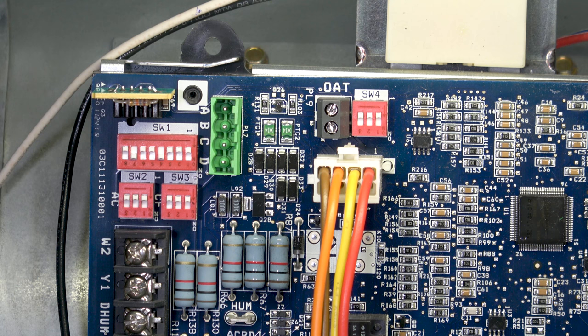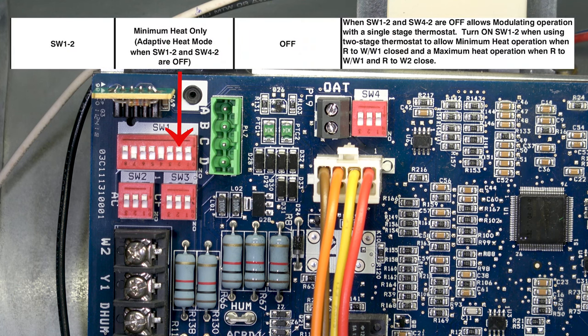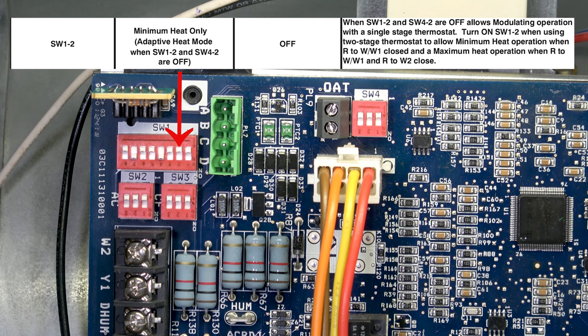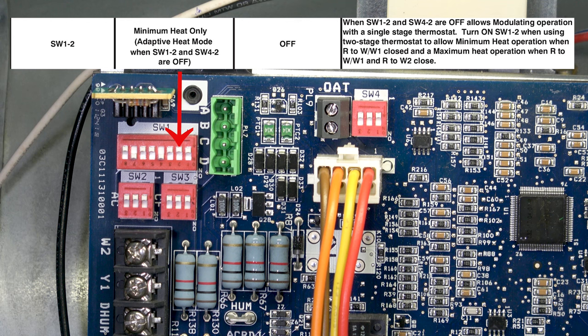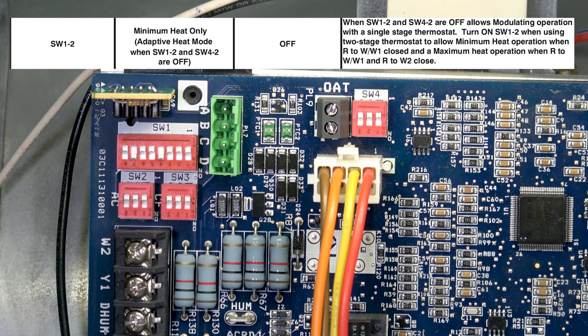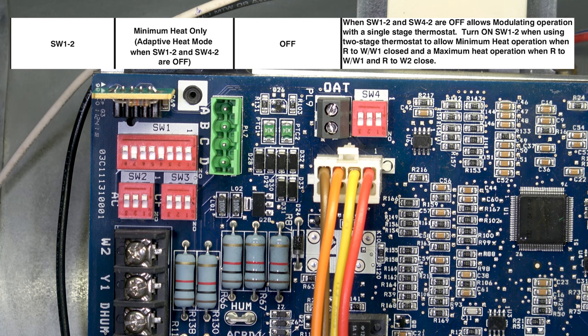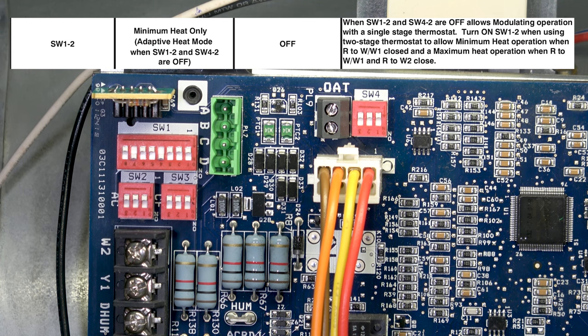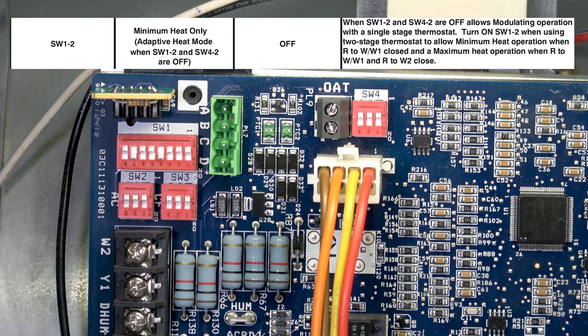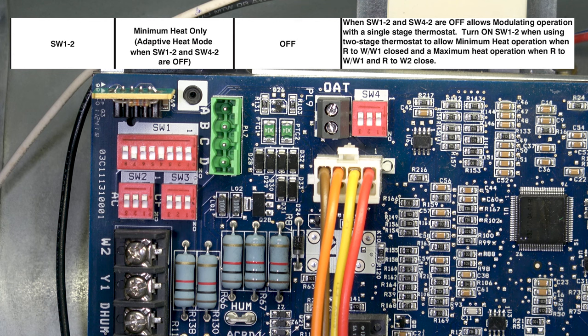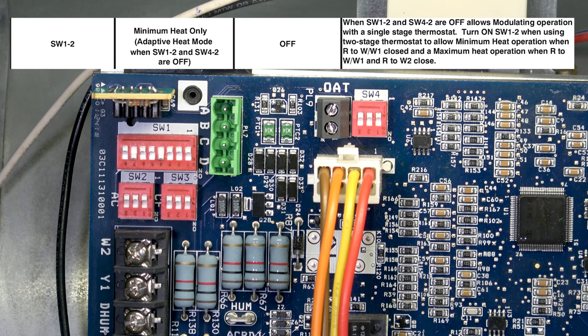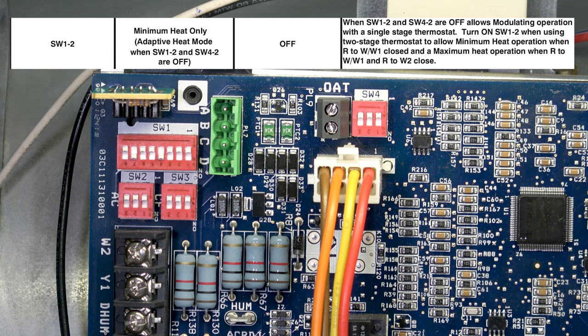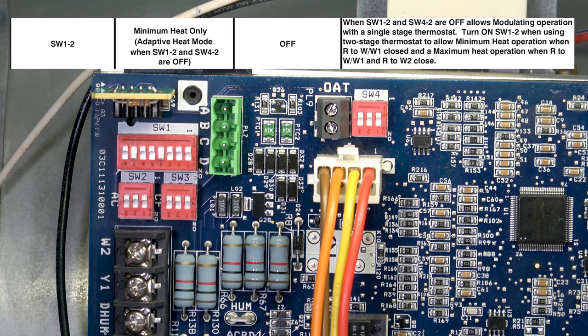Moving to the left is switch two, the adaptive mode switch. This switch is used if you have a single or two-stage stat. If SW1 number two is off, it allows two-stage operation with a single-stage thermostat. If it is on, that means you have a two-stage thermostat. So you would have that on for a two-stage thermostat, off for a single-stage thermostat.